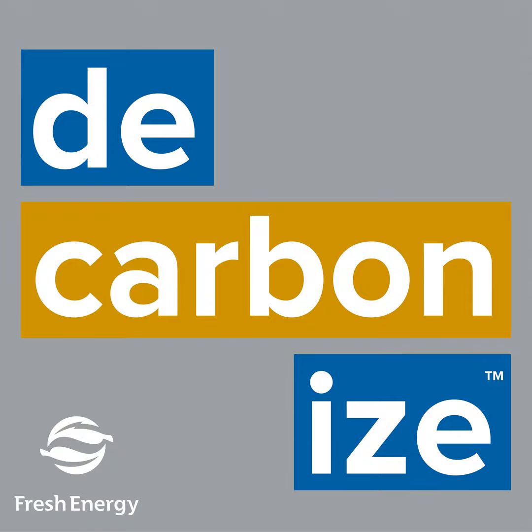When we originally had our bids out, before we found Darcy Solutions, we were looking at somewhere between 70 to 80 wells and a complete tear-up of the parking lot. Now we're down to 4 wells, and we may have even been able to get by with 2, to be honest. That's how well the system can perform. Our approximate annual savings with this new system is around $26,000 per year, resulting in a payback of 7.5 years for the Darcy system. I always tell people we basically have free air conditioning for our 100,000 square foot building.